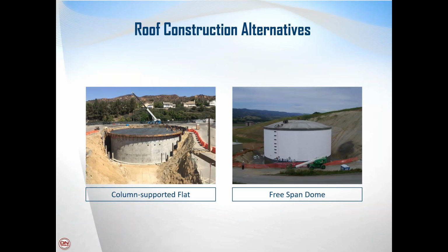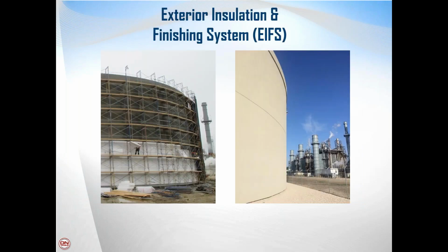And we can also build a tank with a flat roof or a free span dome roof. So on the left-hand side, you're looking at a column-supported flat roof thermal storage tank. This is that 2 million gallon thermal storage tank that was eventually fully buried under the parking lot, but it is column supported, so it has the structural integrity to hold up a fire truck if it were to park on top of it. On the right-hand side, if it's an above-ground tank, typically we will build a free span dome roof, so there's no columns supporting that roof inside. It's just a domed roof where the weight of the roof is supported off of the walls.